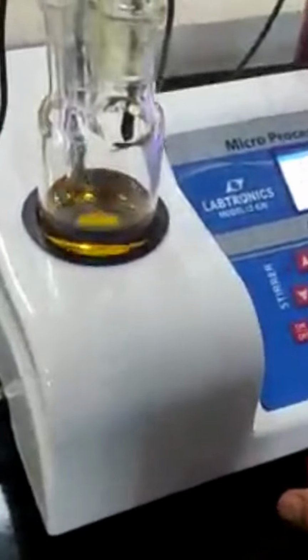So the next option is for calibrate. For the calibrate option, we have to go for option number 3. Press option number 3 for calibrate. Go for factor calibration, option number 1. Then what we have to do is add 25 microliter of H2O by using this micropipette.